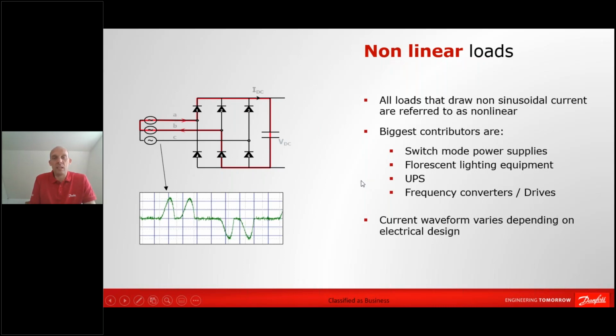So when you have a VSD or a switch mode power supply or a fluorescent light installation or a UPS installation, you will see a circuitry similar to the one that you see on the left hand side. And what we have over here is 6 diodes, and that's the ones marked with 1 to 6. And that is actually the main components of the input stage of a frequency converter or VSD. Additional to that, we have a capacitor in the DC link, and of course you can size this capacitor differently. So depending on your drive brand, you will see different capacitor sizes.